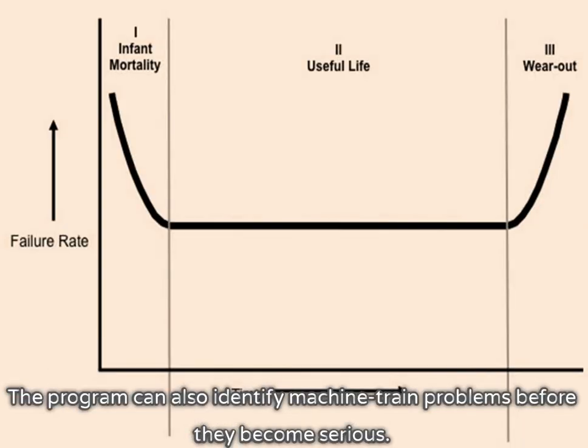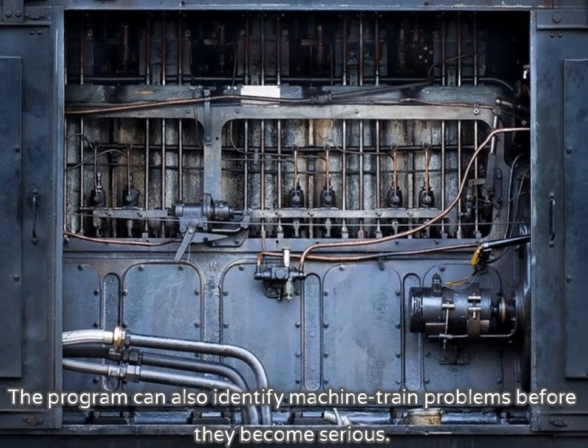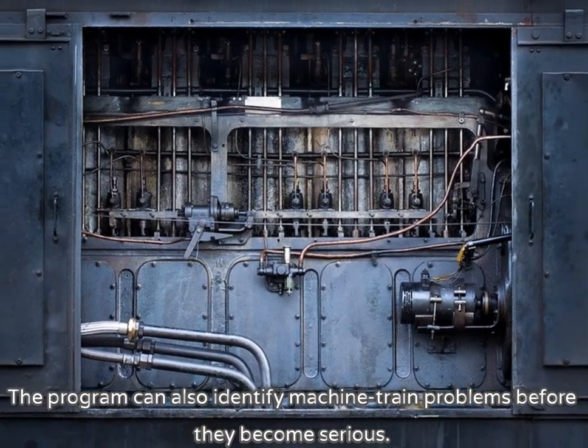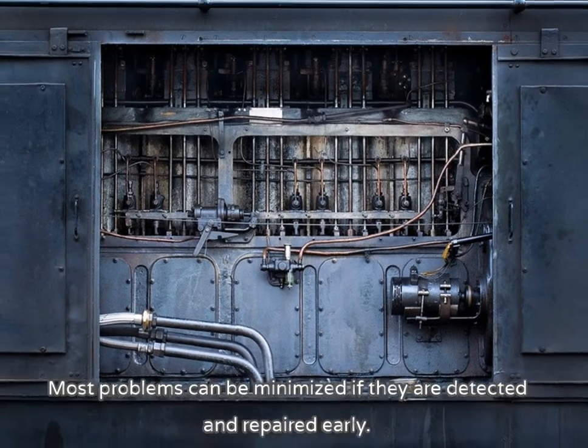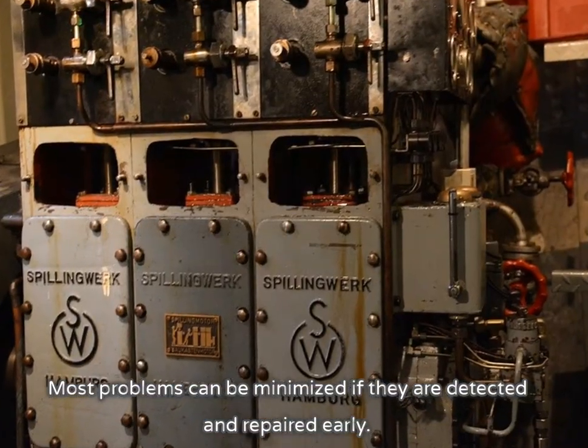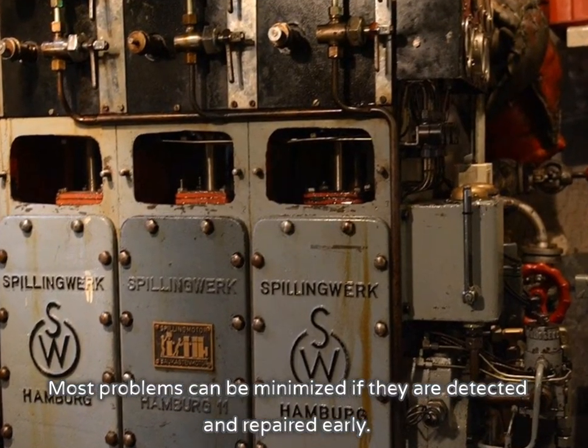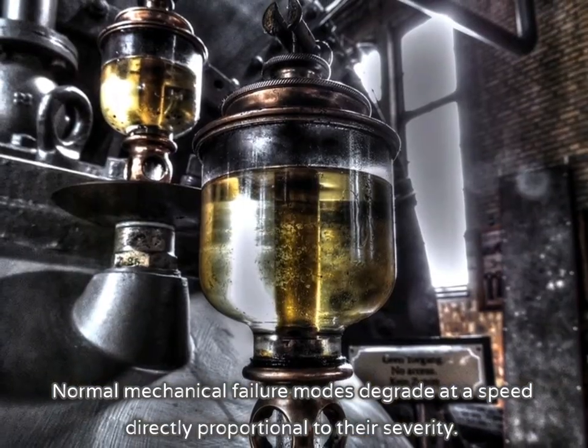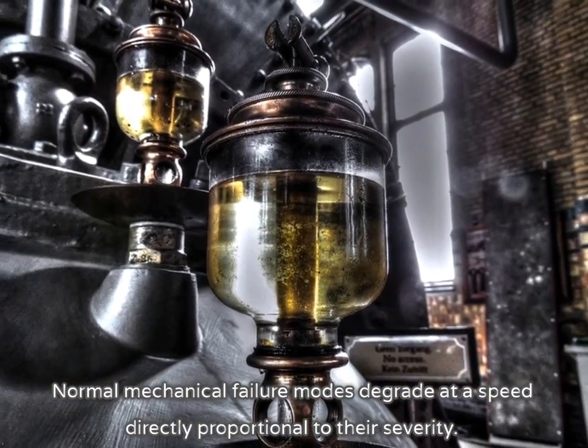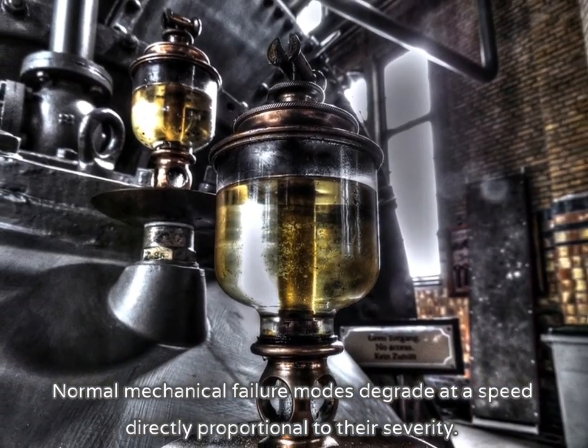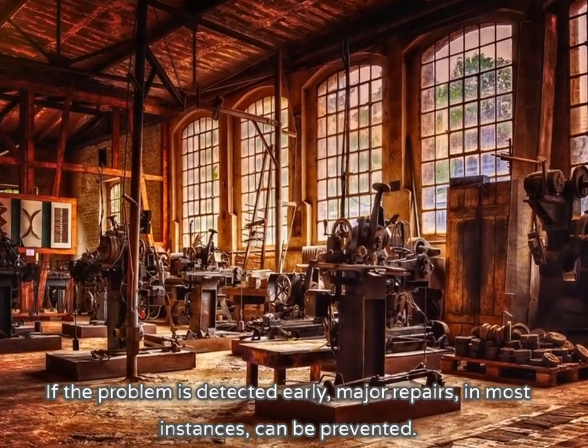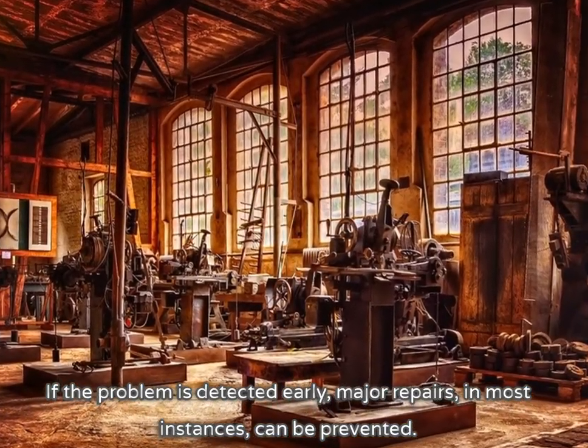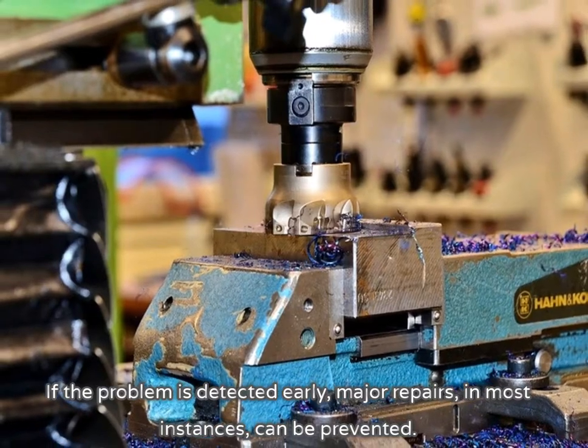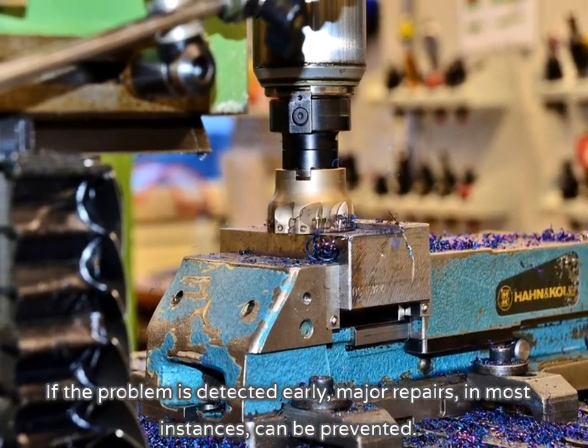The program can also identify machine train problems before they become serious. Most problems can be minimized if they are detected and repaired early. Normal mechanical failure modes degrade at a speed directly proportional to their severity. If the problem is detected early, major repairs, in most instances, can be prevented.